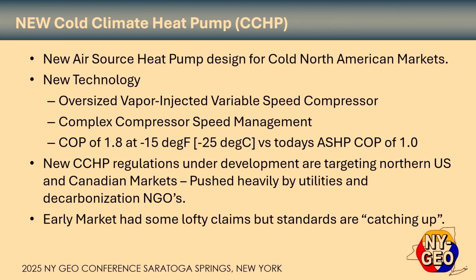And the COPs they're touting now are roughly at a minimum about 1.8 at minus 15, and the COP of the air source heat pump today is like 1 at that particular point. So almost double the COP there.